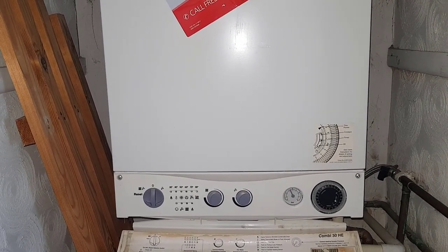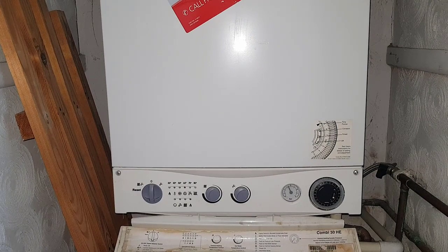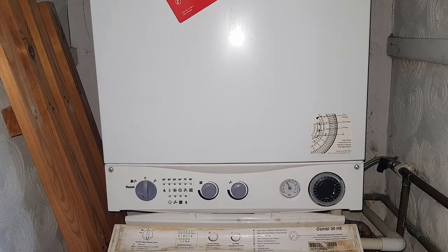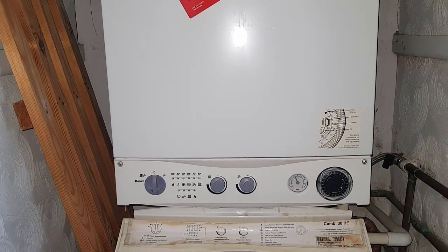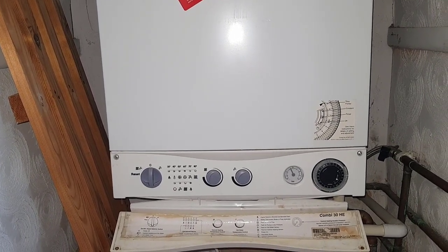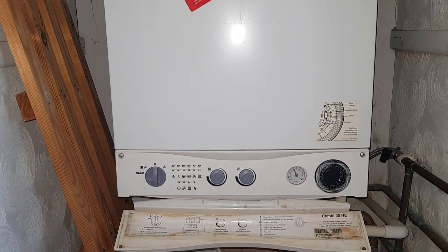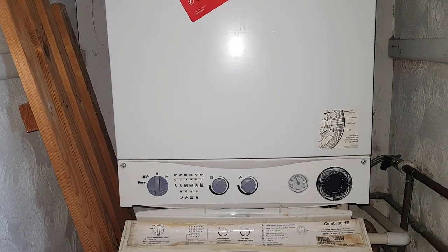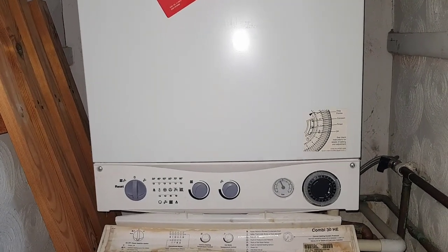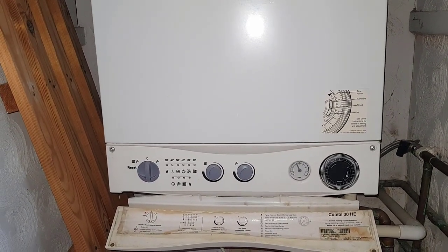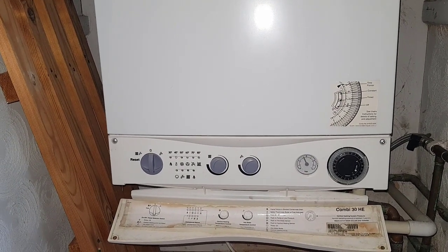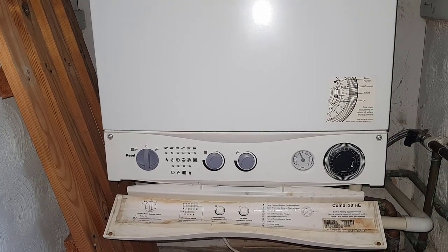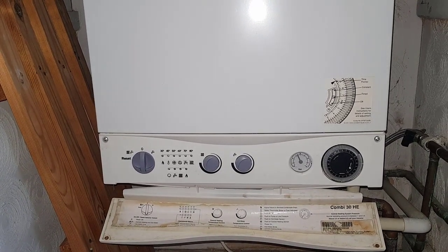Okay, Mr. Customer, if you can just tell us what's happened, the reason why you've called us out. Okay, we can't get any hot water. The boiler is permanently making a noise, whether it's the fan or the pump or whatever. It's permanently on, making a noise. When you reset it, it still doesn't sort of set itself. If you try and run the water, it doesn't fire up. But on the warning lights, there's no warning light to come on saying the pilot light or anything else isn't working.